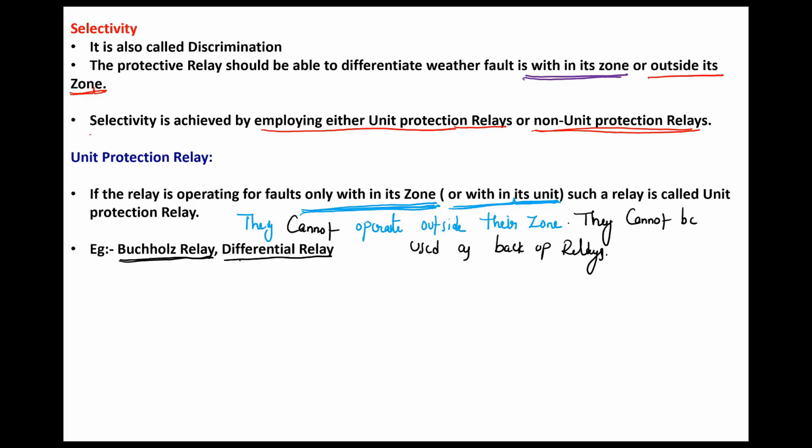One more is differential relay, current differential relay or voltage differential relay. They can only operate for the faults within their zone. Outside their zone, they will not or they cannot operate. Understand?